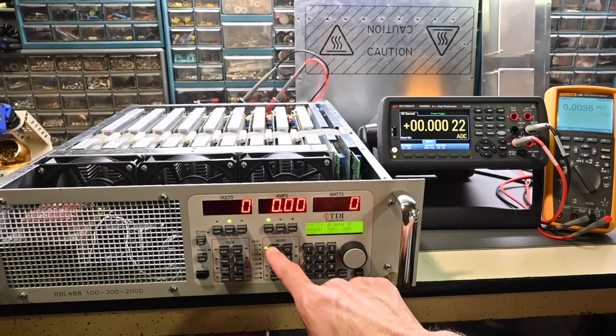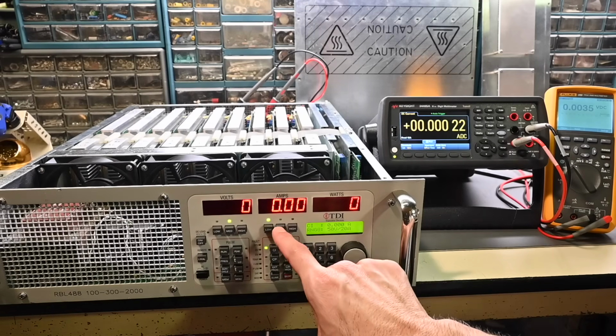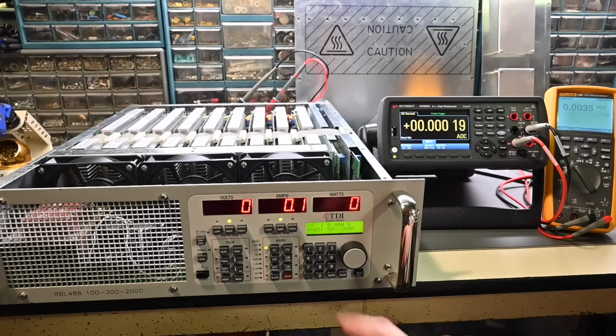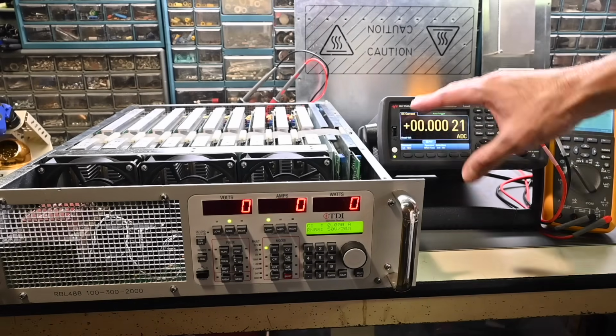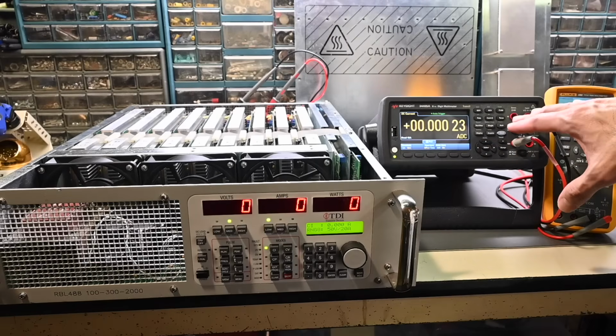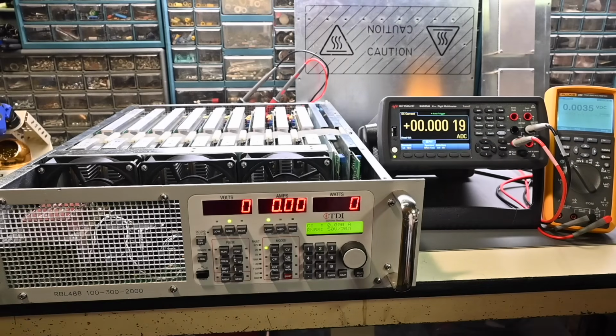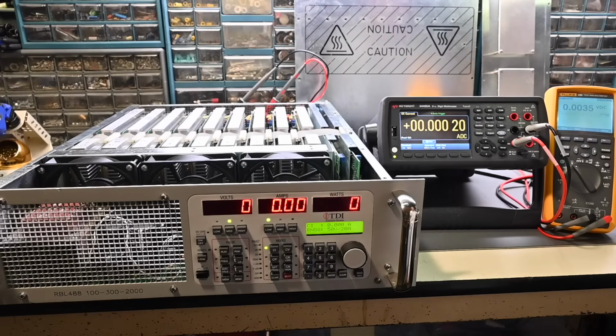And then right here for the current, it's in low, so that's 20 amps maximum. Medium is 200 amps, and the high range, 300 amps. So low is perfectly fine. I won't be going anywhere near 20 amps because this digital multimeter and the current measurement is limited to 10 amps maximum. So we don't want to exceed that. All right, so let me go over here and give this some voltage.